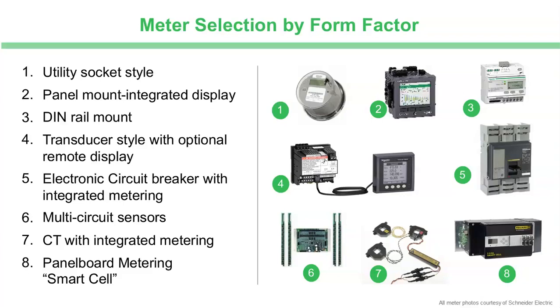And then 7 and 8 are kind of a retrofit and a panel board plug-on style. So 7 is showing the current transformers and voltage that go to a metering embedded inside of the CTs themselves. So there's a lot of convenient ways of retrofitting metering. And then the final one there, 8, is an example where the metering has actually been built into a module that plugs on like a circuit breaker in a panel. Those are being called in the industry smart cells. It does help you avoid having to extend either the side or the tops or bottoms of your panels in order to be able to fit metering. So there's some innovative ideas out there to help you solve your problems.